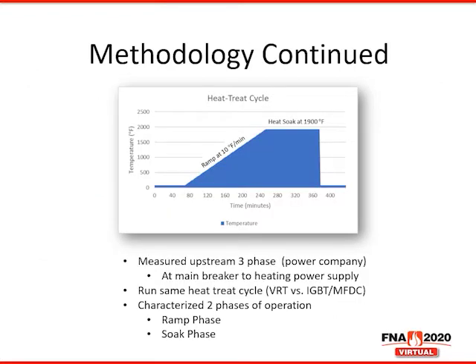In order to compare the two power supplies, we ran the same cycle with the VRT in place, and then ran that same cycle again with the IGBT MFDC power supply in place. You can see from our heat treat cycle here that we ran at a ramp rate of 10 degrees Fahrenheit a minute up to a soak phase of approximately 1900 degrees Fahrenheit. We then measured upstream three-phase power, essentially what the power company sees, at the main breaker that went directly to the heating power supply. We then characterized these two phases of operation. We looked at the ramp rate, and then we looked at the soak phase.